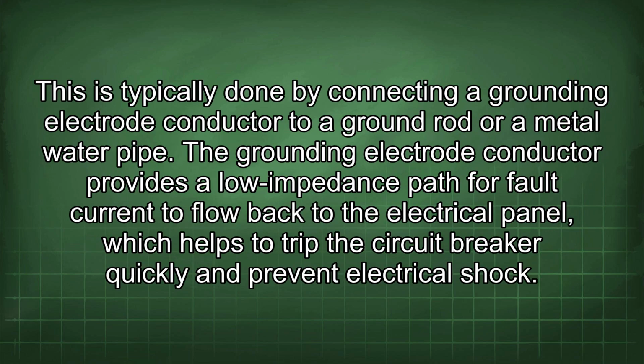This is typically done by connecting a grounding electrode conductor to a ground rod or a metal water pipe. The grounding electrode conductor provides a low impedance path for fault current to flow back to the electrical panel, which helps to trip the circuit breaker quickly and prevent electrical shock.